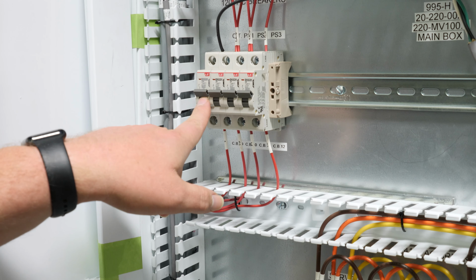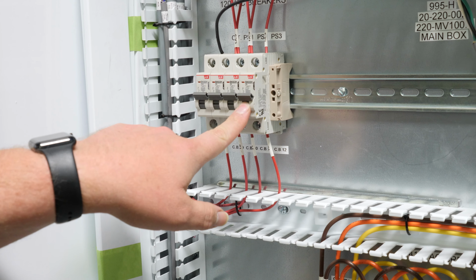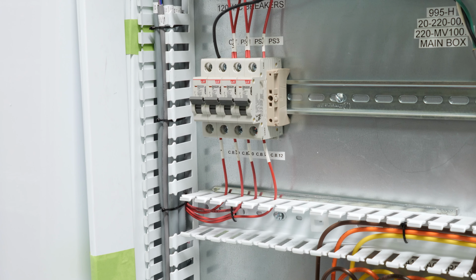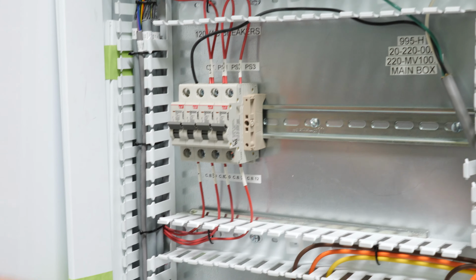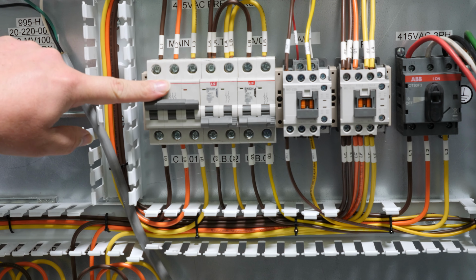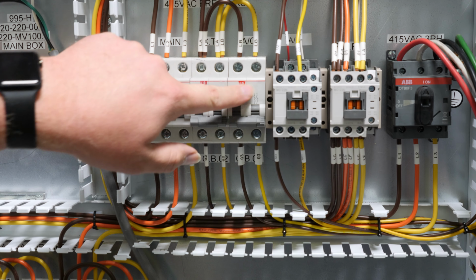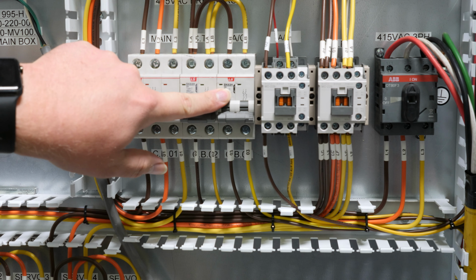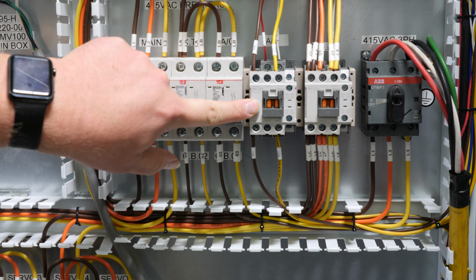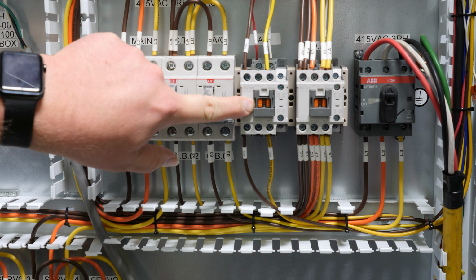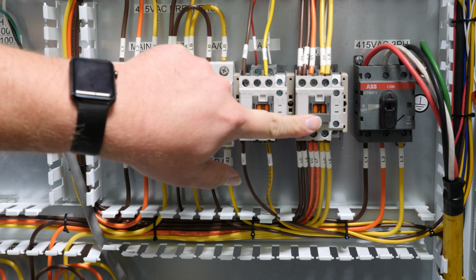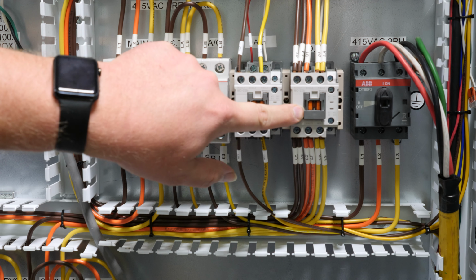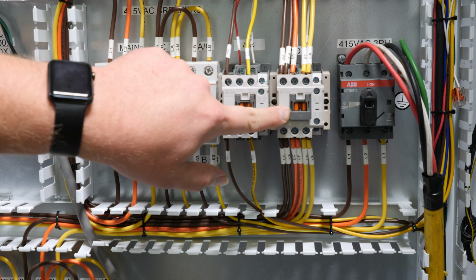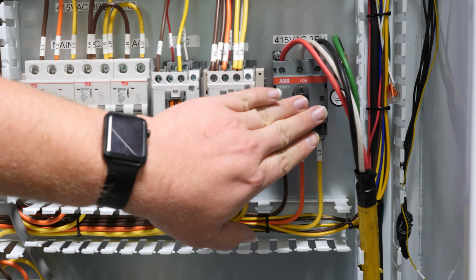Down here we have our breakers. So here we have CT1, PS1, PS2, PS3. So these are all the breakers for the power supplies and the control transformer. We have our main circuit breaker here, our main control circuit and AC unit circuit breakers here. We have a contactor for the AC units for turning them on and off. Then we have the PDR, which is our main power. That's providing 3-phase power for the servo amps and the VFDs. This is the main disconnect, which would have the shaft coming out of it connecting to the handle on the door.